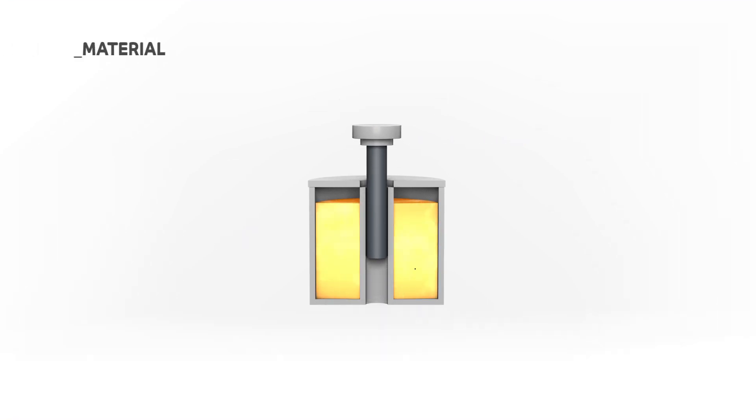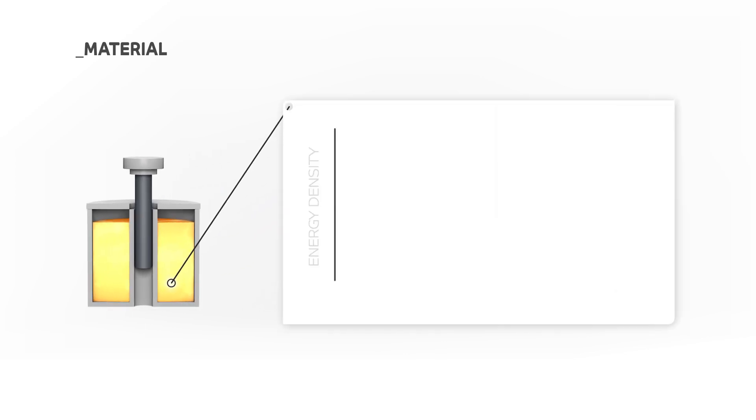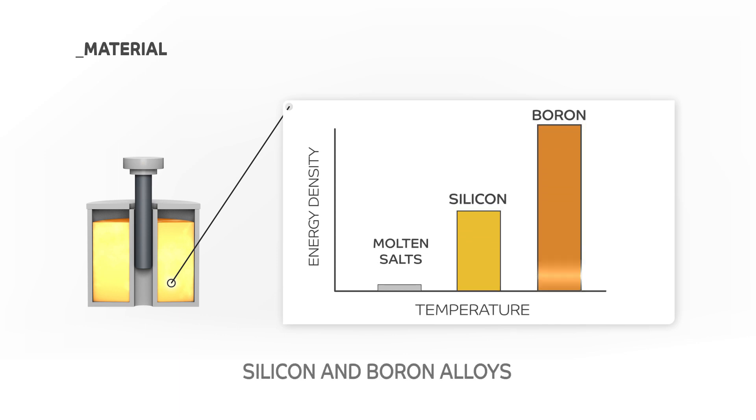The energy storage capacity of the system relies on the phase-change material thermal properties. In this regard, novel silicon and boron alloys with melting temperatures above a thousand degrees centigrade are being investigated to reach energy densities over one kilowatt-hour per liter, a value that is two times greater than the best-performing lithium-ion batteries, and ten times greater than that of currently used molten salts.